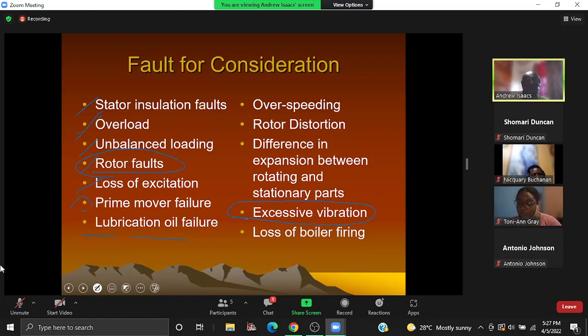Well, I have to give credence to the fact that you're all very young, so you wouldn't be familiar. We had a significant outage some years ago where we lost 30 megawatts because of a problem like this, all right? One of the generators at JEP was damaged, and they had detected the vibration, but for whatever reason, it was not acted upon, and we lost that generating unit, and so we were struggling in terms of power generation for quite a while. All right, so I went through all of that talking because I know that you were writing this stuff. So these are the many issues that can confront you for a generator, which you have to then speak to.